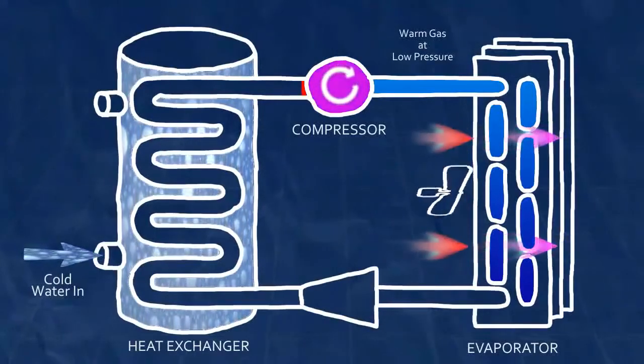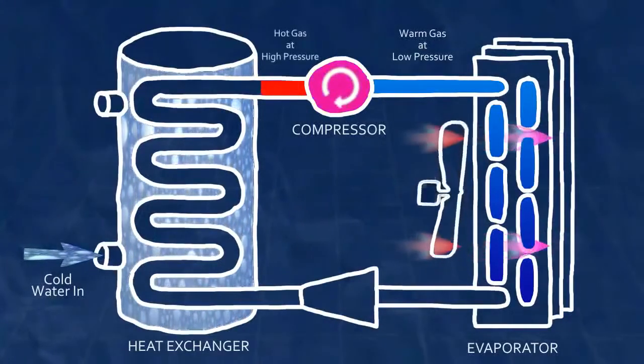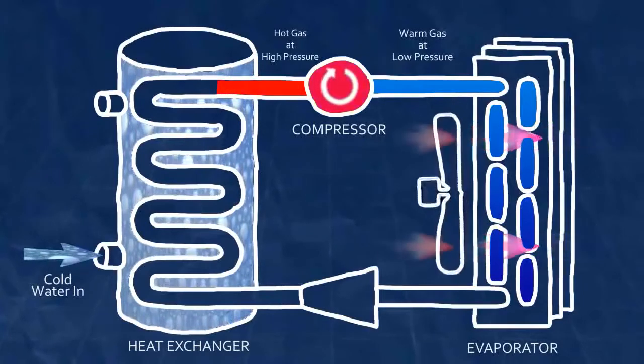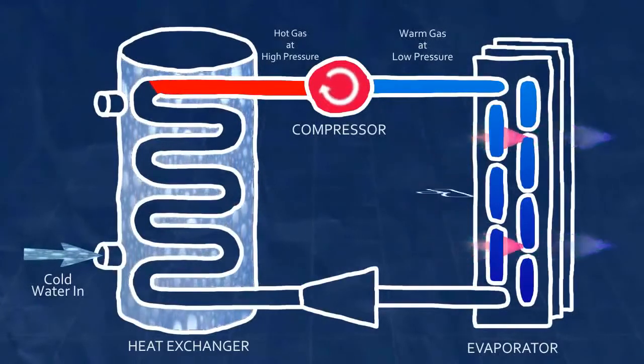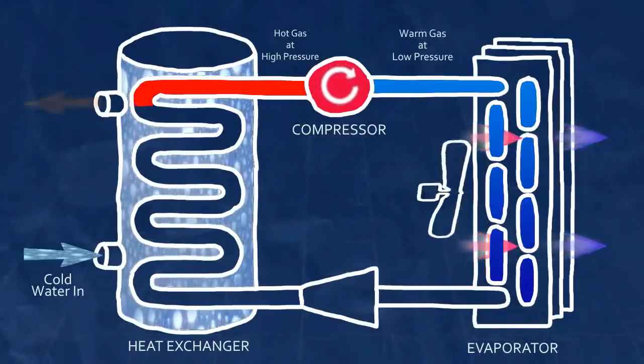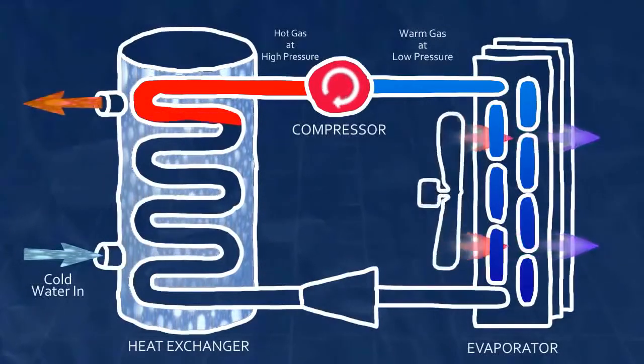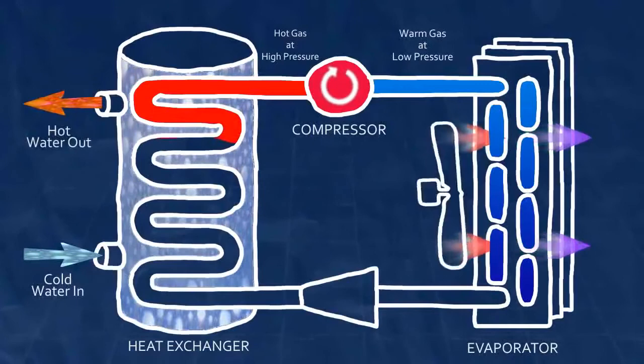The compressor next forces the now high-temperature, high-pressure gas further along the cycle into another heat exchanger called the condenser. The condenser is in contact with the water and the hot gas now gives up its heat to the colder water.